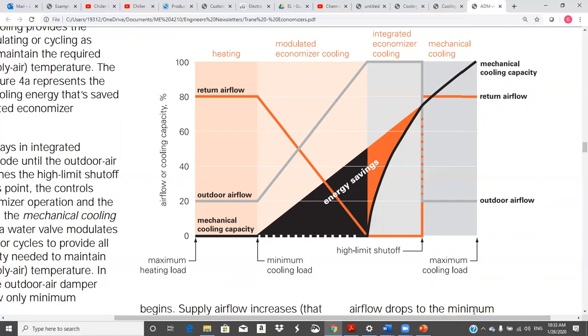And then we get to minimum cooling load. Well, this is still pretty cold. You know, a big building, interior core, heat starts building up. So we hit a minimum cooling load. And so what do we do? We start increasing the amount of outside air so that we can cool with outside air, which decreases the return air. Because remember, this plus this is supply going out to the space. Well, it gets warmer. And notice this black area indicates energy savings because we're not running a compressor or a chiller or anything. We're just doing this with the ventilation, okay? And so we get more and more load, so we get more and more ventilation air, outside air, economizer air, and less and less return air.